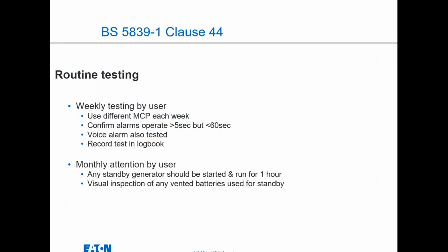So they should be doing their weekly testing, and that's usually by the end user, and that's different call points each week. Confirm alarms operate. The voice alarm, if there is one, needs to be tested, and any records should be in the logbook. So again, making records of making the tests and making sure they happen. Monthly, they should be checking any standby generators, and they should be run up for an hour, and then visual inspection of any of the batteries that they're using, if they've got central batteries and stuff like that.